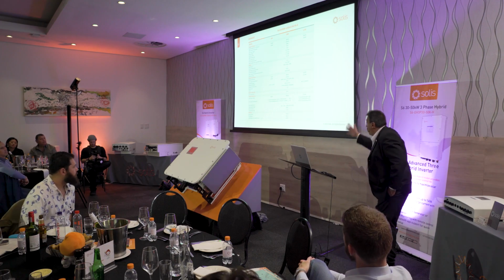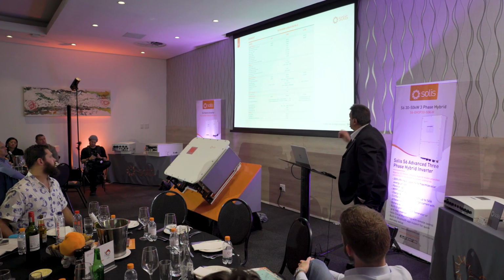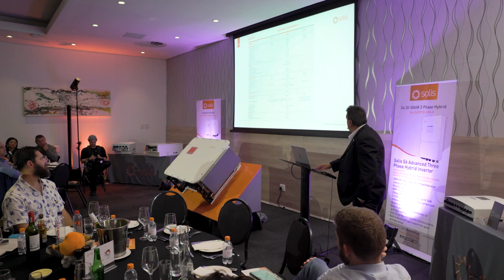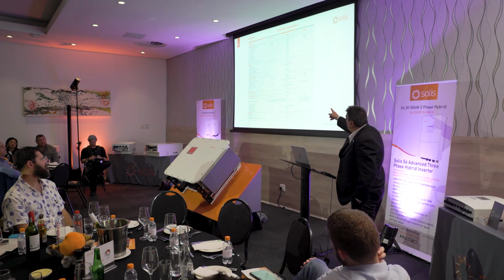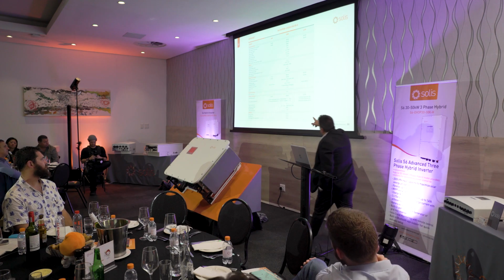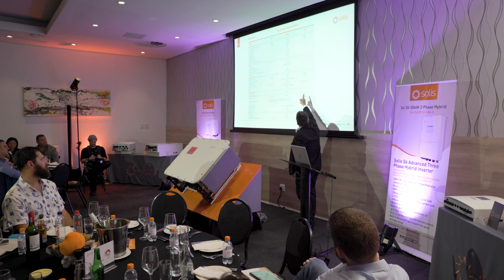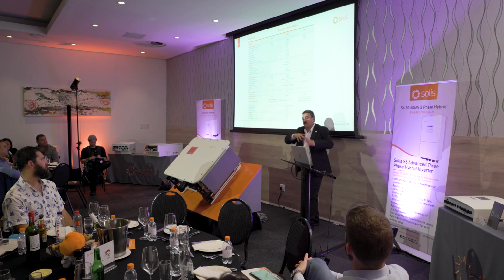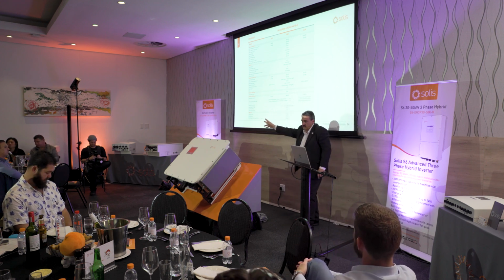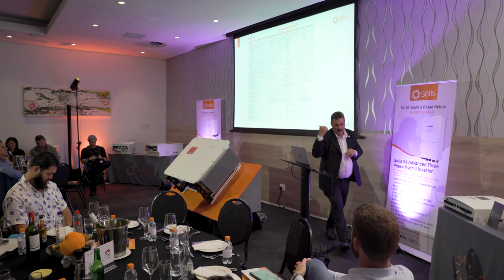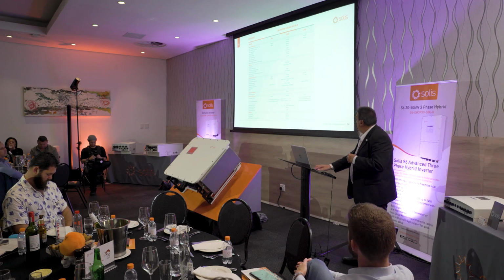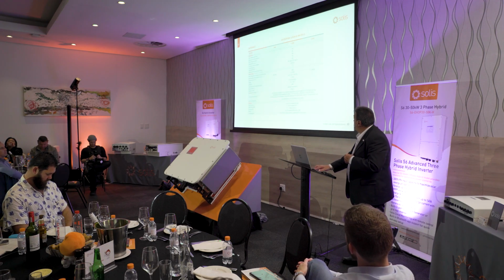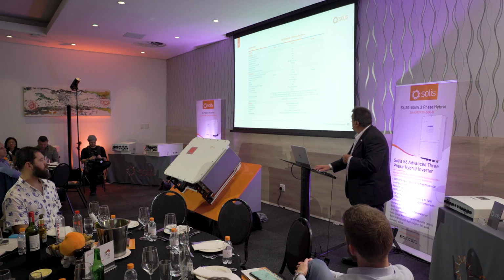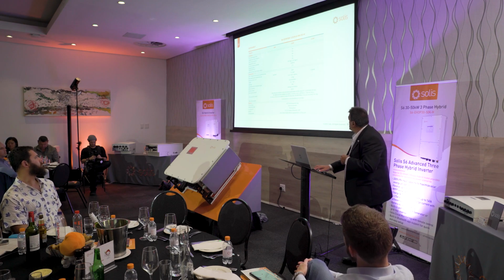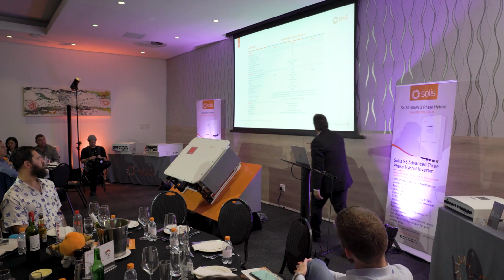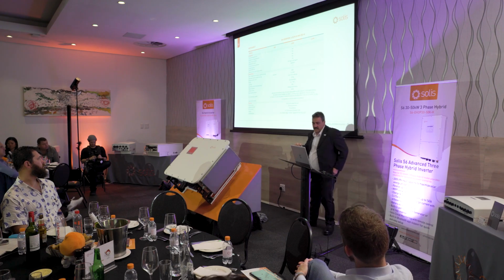I'm not going to go through the whole data sheet, but it's pretty impressive. From the grid side, AC output is 125. As we discussed, you can't take 250 kilowatt and send it all back to the grid, but 125 kilowatt you can. So what is the 100%? That's 41.66 kilowatt per phase.